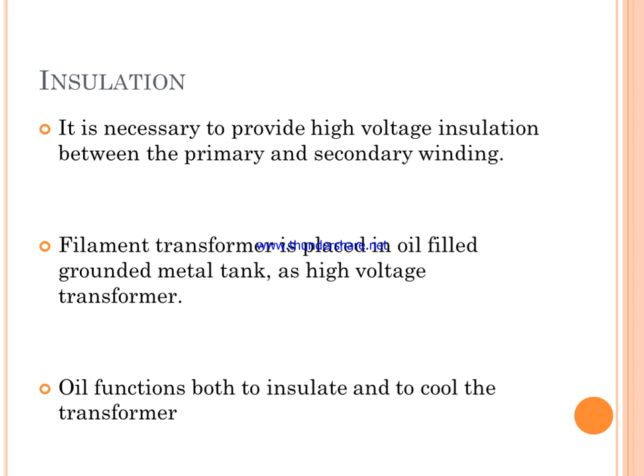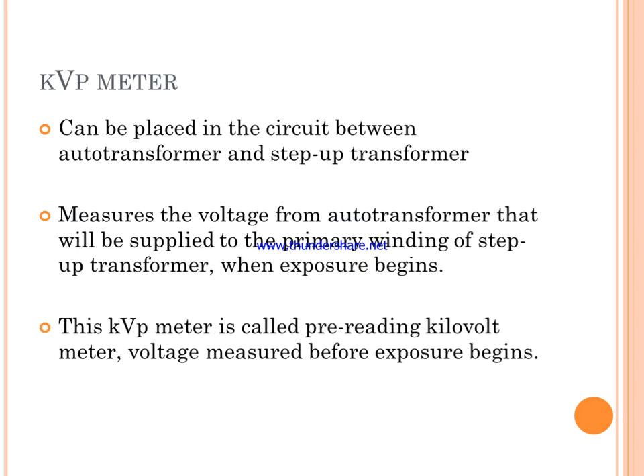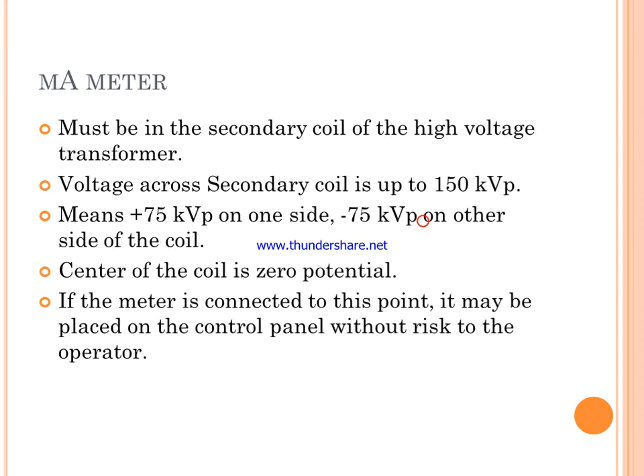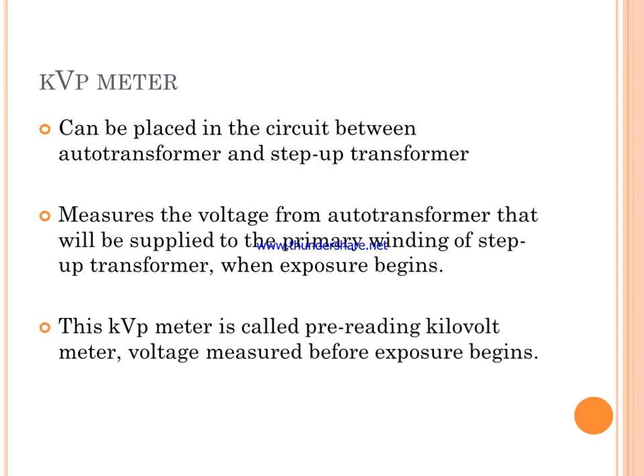Insulation is very necessary to provide high voltage insulation between primary and secondary wiring. The filament transformer is placed in an oil-filled grounded metal tank, as is the high voltage transformer. The oil functions both to insulate and to cool the transformer. The kVp meter is placed in the circuit between the auto transformer and the step-up transformer.